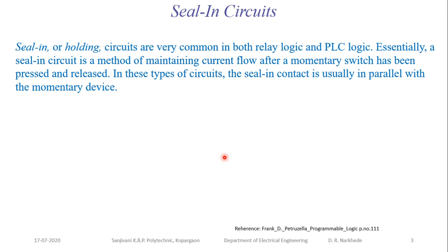To avoid that, we never recommend using press and hold type switches. Instead of that, we recommend press and release type switches. What happens in the press and release type switches? When the switch is pressed, at that time the machine will start.